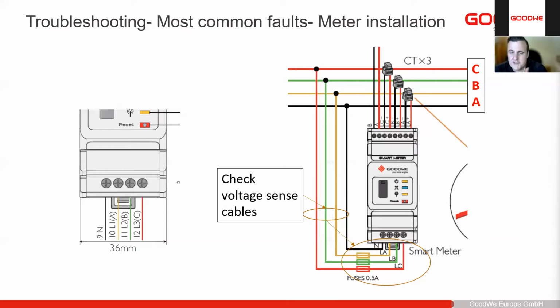Then normally the first instinct is that the CT is on the wrong way, or the polarity on top is wrong. But it's never been the case. I've never found that ever. It's always the voltage sense that needs to be fixed. We double check that our correct voltage sense is on the correct CT.